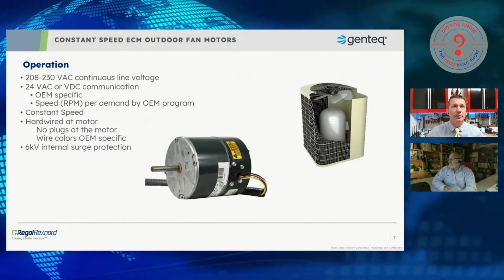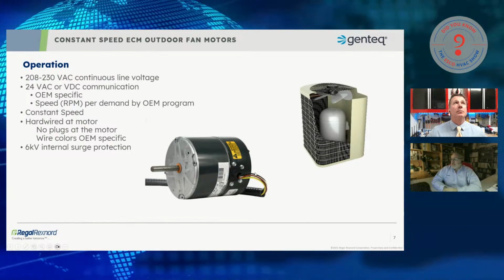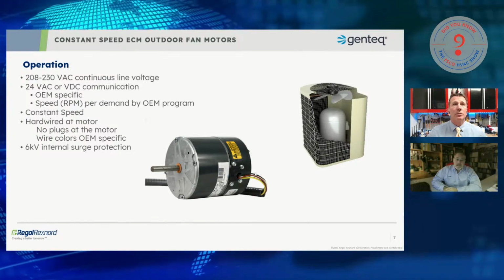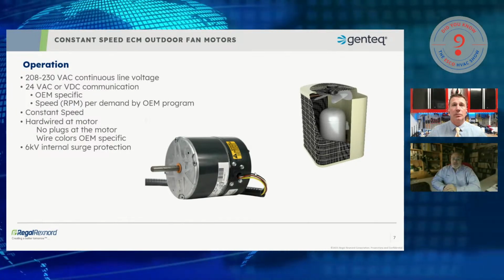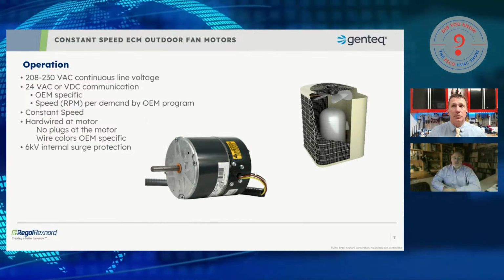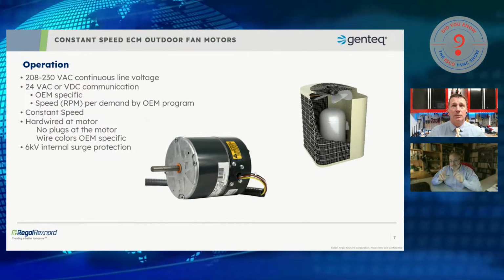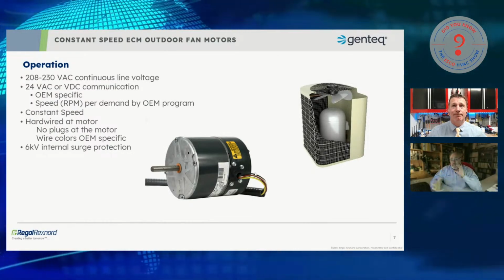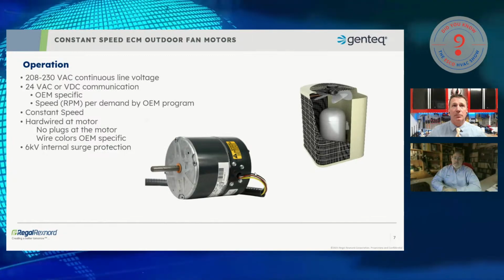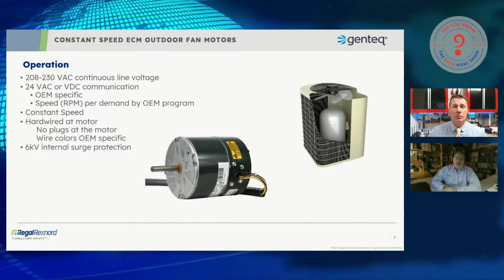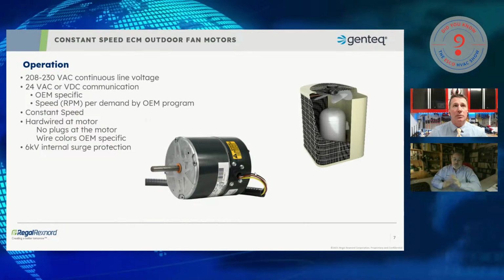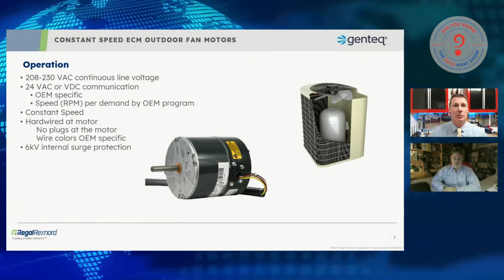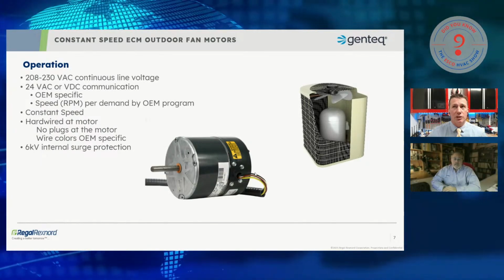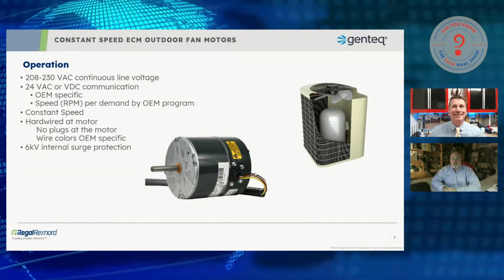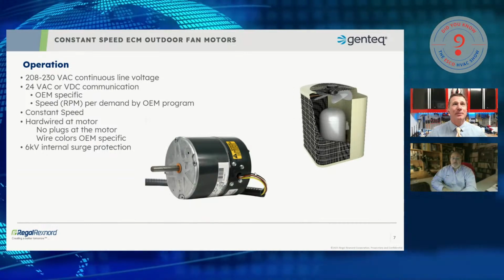Yeah, absolutely. It's understanding. So last but not least, I do want to mention that these motors do have a 6,000 volt internal built-in surge protection. So it's not a surge protector component, so to speak, but it has built-in components to allow it to handle 6,000 volts of surge. We get asked that question quite often, especially from certain regions of the U.S. where voltage and lightning and natural events seem to cause issues with that. Sure. It is built into the motor.